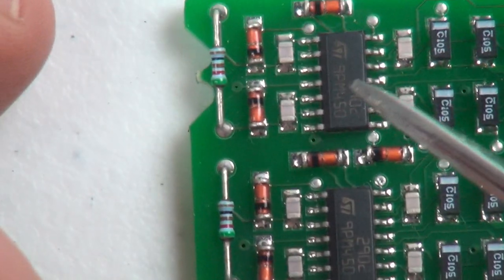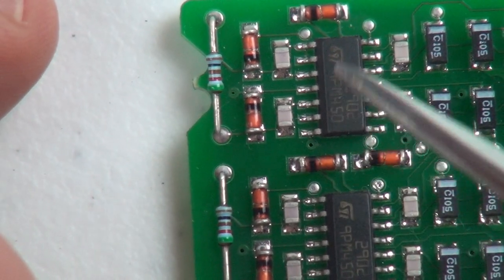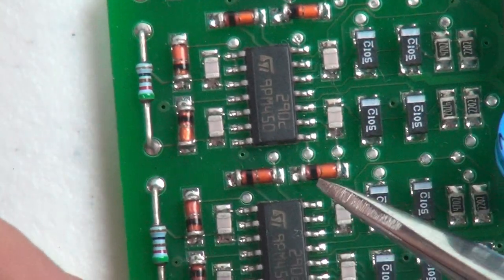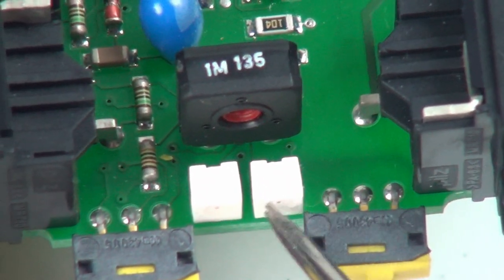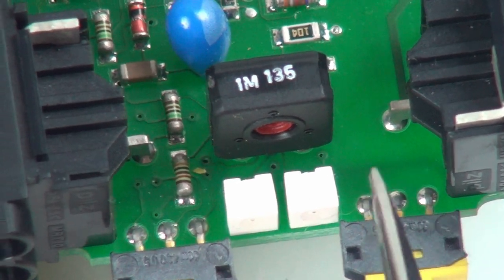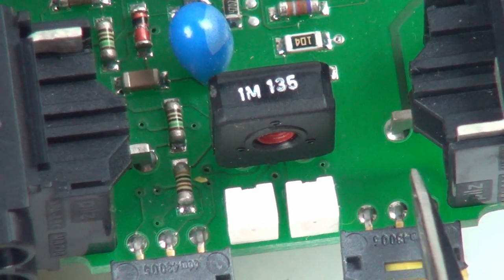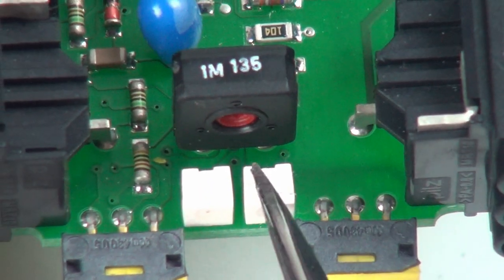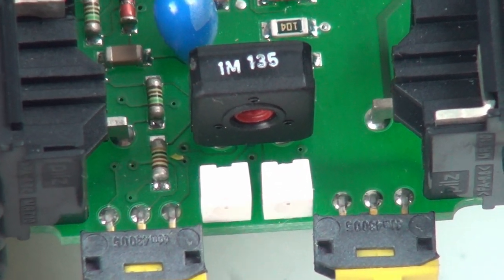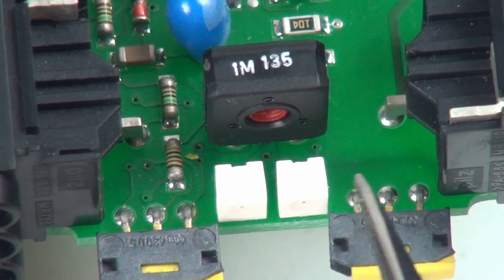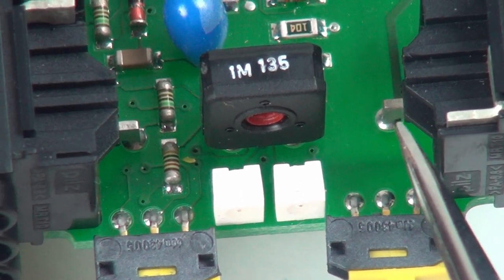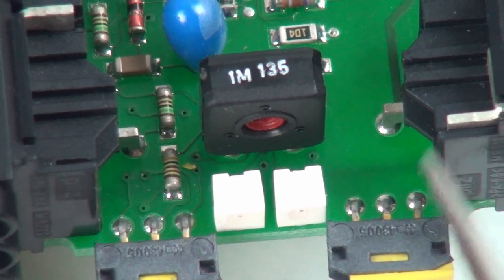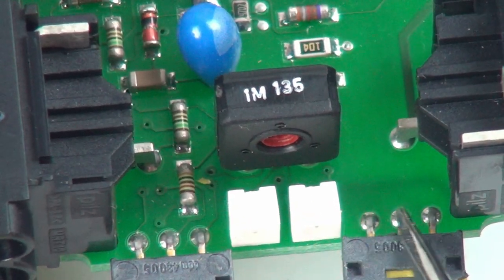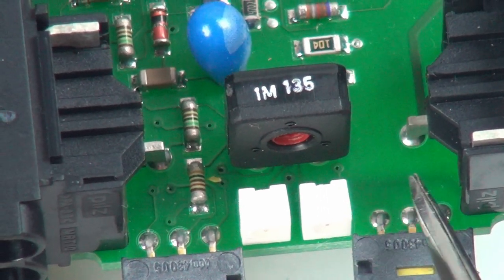Well, what can I think of what it's called now? Why my voltage pattern is all distorted or something like that, or all the collective voltage is too low, or what I tripped on, etc. An analog circuit wouldn't be able to tell you that just through a single light. So maybe multiple lights, maybe that's something PILZ could have done, is to have like three lights here besides the power light that are like, my voltage too low, or my voltage too high, or I have exceeded my asymmetry. That's the word I was looking for, asymmetry. You know, where the sinusoid is distorted or something like that.